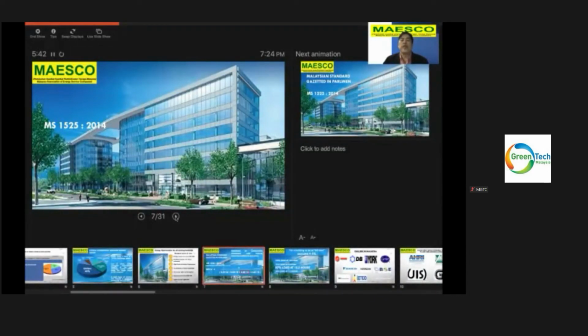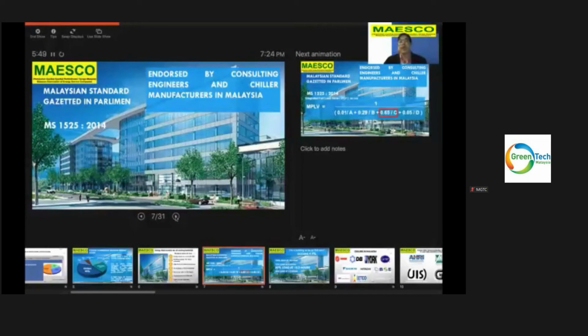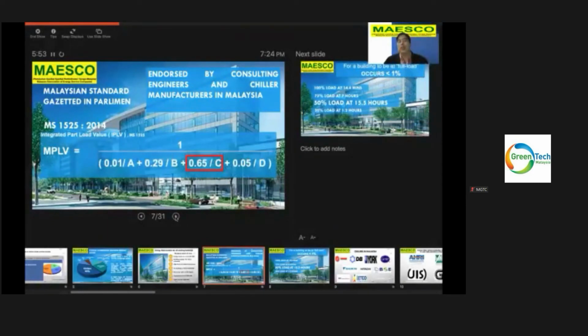In MS 1525:2014, the Malaysian standard gazetted in Parliament, endorsed by consulting engineers and chiller manufacturers in Malaysia, this is the formula that we use to study the chiller operation in any building. This is the Integrated Part Load Value, or IPLV. If you notice, there's 0.01A, 0.29B, 0.65C, and 0.05D. Now, what does this all mean?